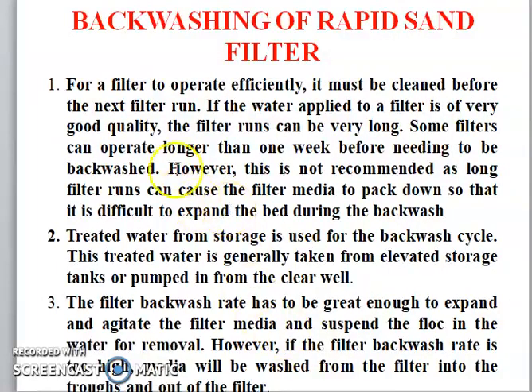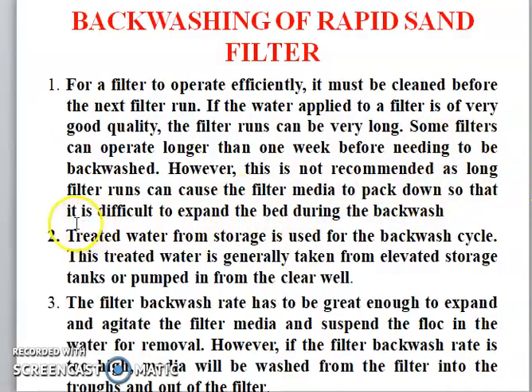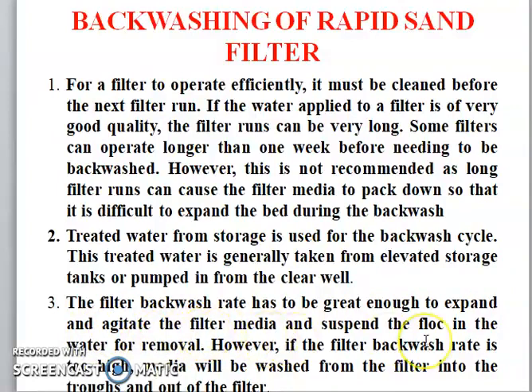Back washing of the rapid filter: for a filter to operate efficiently, it must be cleaned before the next filter run. If the water applied to the filter is of very good quality, the filter run can be very long. Some filters can be operated for longer than one week before needing to backwash; however, this is not recommended as a long filter run causes the filter media to pack down, making it difficult to expand the bed during backwash. Treated water from storage is used for the backwash cycle, generally taken from a clear water storage tank or pumped from a clear well. The filter backwash rate must be great enough to expand the filter media and suspend the floc in the water for removal. However, if the filter backwash rate is too high, media will wash out of the filter into the troughs.